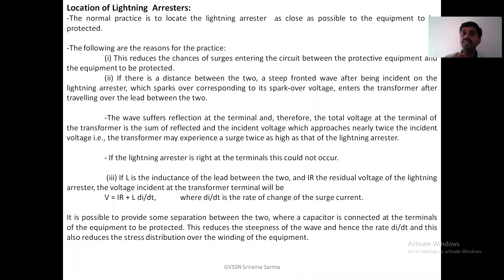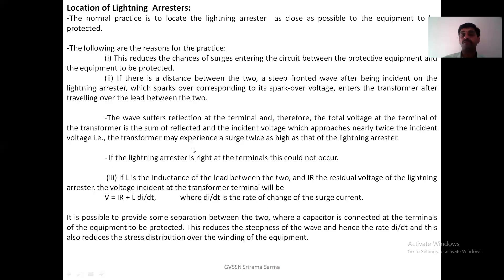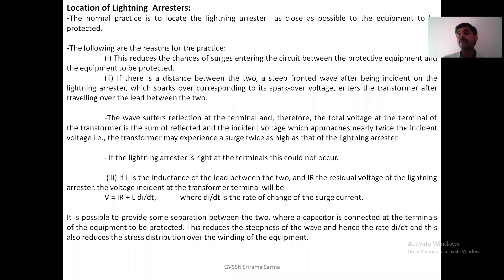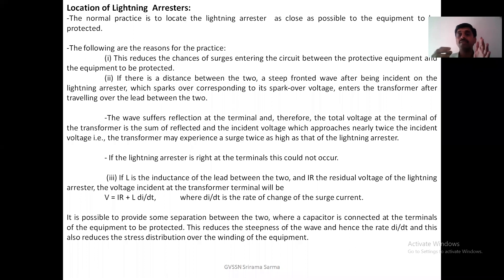That means after this, it enters the transformer because there is a gap between those two. Then that wave suffers reflection at the terminal end. Therefore, the total voltage at the terminal of the transformer is the sum of reflected and incident voltage. As you know from traveling wave theory, the reflected voltage plus incident voltage — finally it becomes twice the incident voltage. So if there is a gap between the lightning arrester and the transformer, this voltage suffers reflection, and the transformer may experience a surge twice that of the lightning arrester.